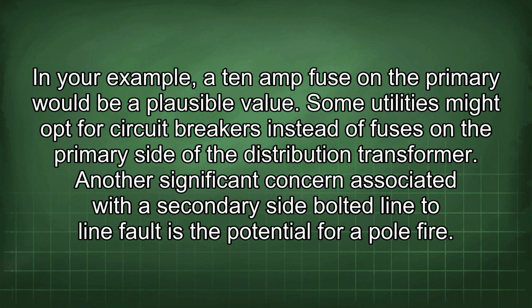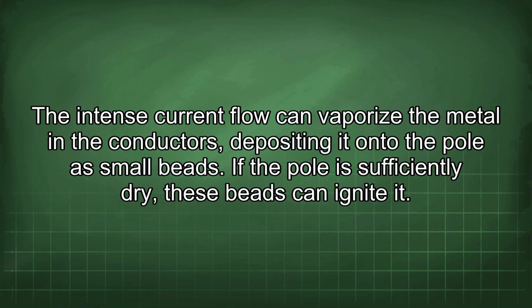Another significant concern associated with a secondary side bolted line-to-line fault is the potential for a pole fire. The intense current flow can vaporize the metal in the conductors, depositing it onto the pole as small beads. If the pole is sufficiently dry, these beads can ignite it.